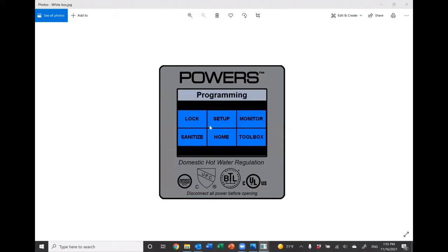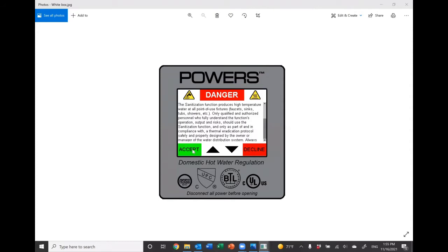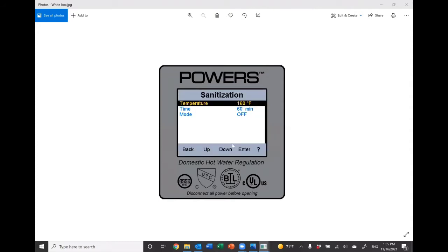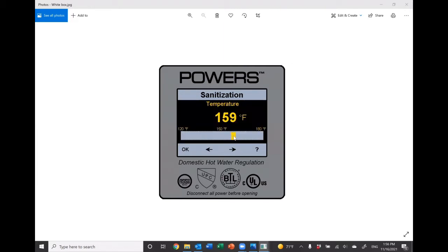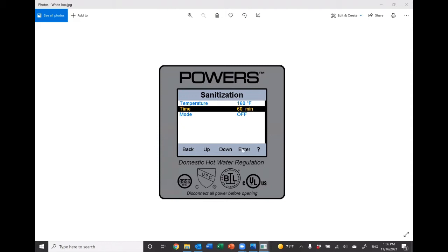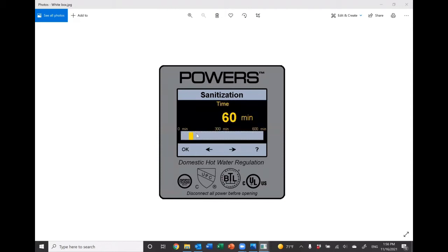Going back into programming, there's also the sanitization mode. Especially with increased concerns over things like Legionella, a lot of buildings are calling for an annual or semi-annual, maybe quarterly, monthly, depending on the facility and what their concern is, of running hot enough water through the entire system to kill off any bacteria that's growing in it. So if you're on the Powers Intellistation, you just go into your sanitization mode, you select your temperature, enter, and say we want it to do it at 160 degrees, as long as I'm supplying the hot side with 160 or better. I can raise it to that temperature, hit OK, go to your time for that sanitization mode, enter, let's say I want to run it for 35 minutes, OK.